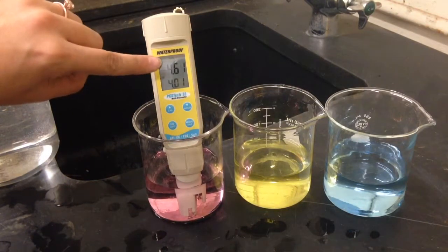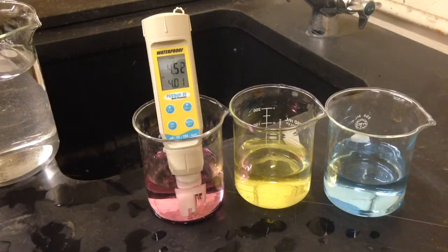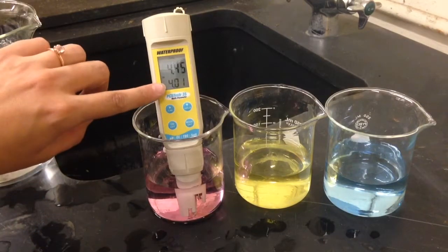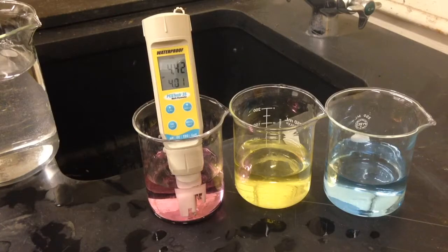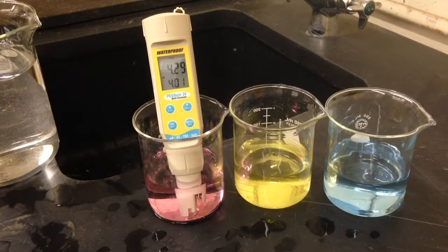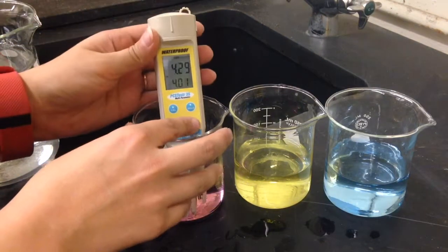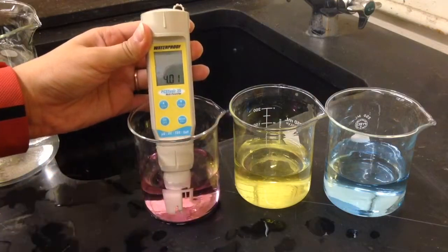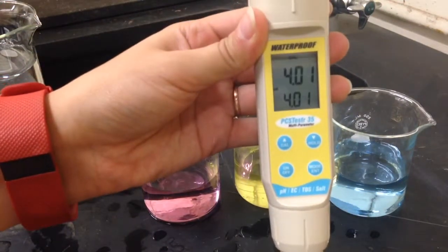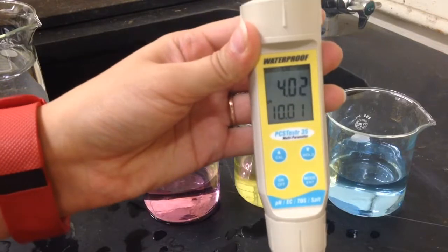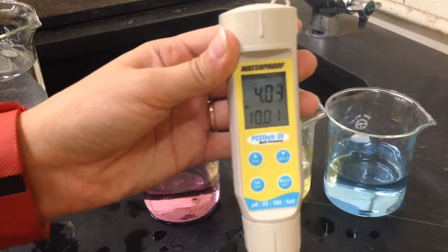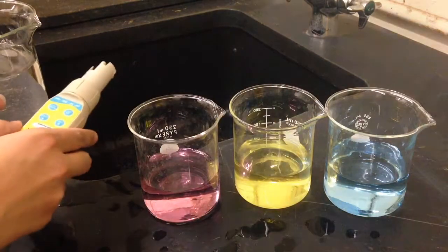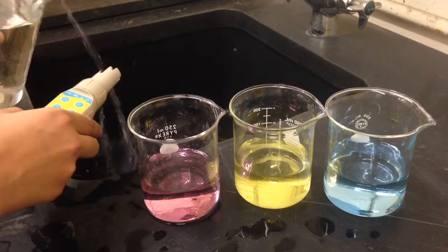Again, the primary display is going to read the actual value of the container, and the secondary display will read the closest pH calibration standard. We are going to wait for the primary display to stabilize. Once the primary display stabilizes, we push the Mode Enter button. Again, the primary display will flash, and the secondary display will read the other calibration standards in which we can use to calibrate our meter. Before using the last standard, we are going to rinse our meter.